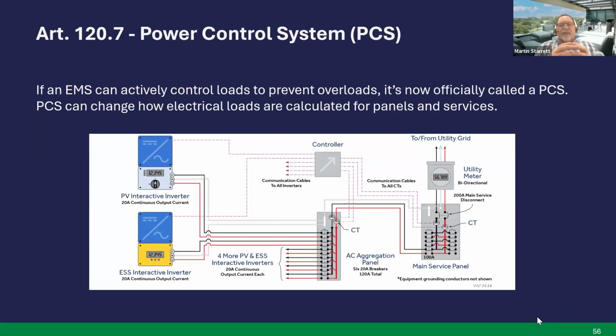Power control systems, 120.7. If an energy management system can accurately control loads to prevent overloads, it's now officially called a power control system. A power control system can change how electrical loads are calculated for panels and services. We're getting into solar and battery, and a lot of our houses and commercial projects are on these energy management systems, and a lot of these use power control systems. So you're able to do some different load calculations based on how you install these items in your electrical system. But the whole purpose of these power control systems is controlling the overloads. Next slide, please.